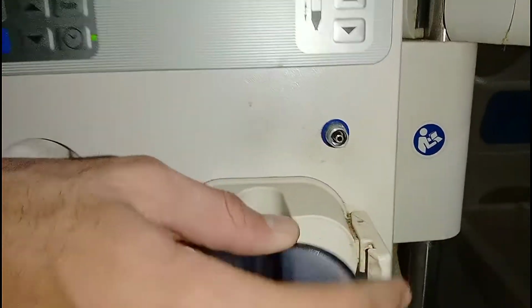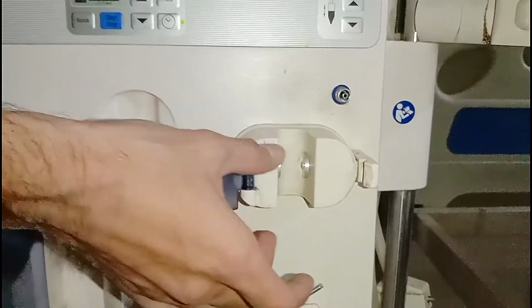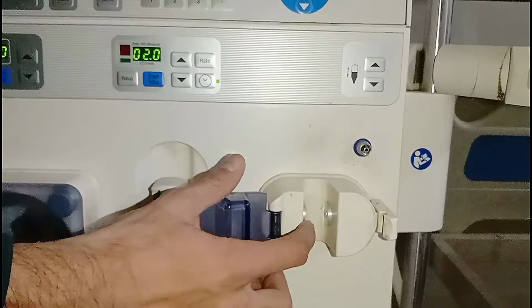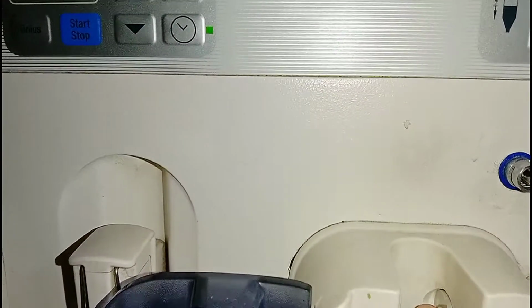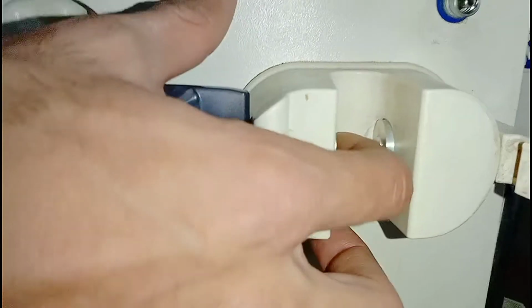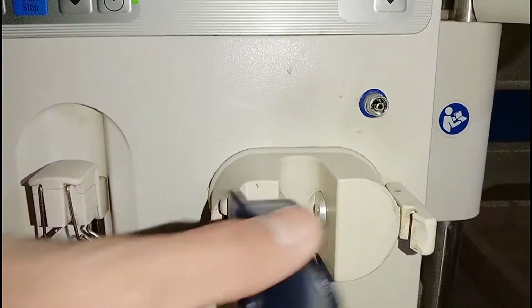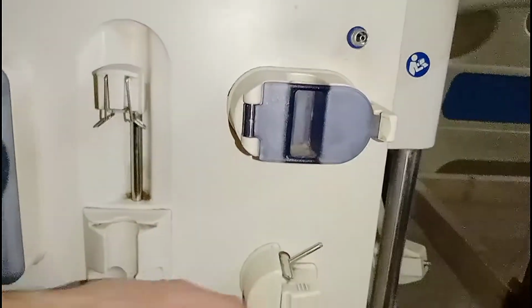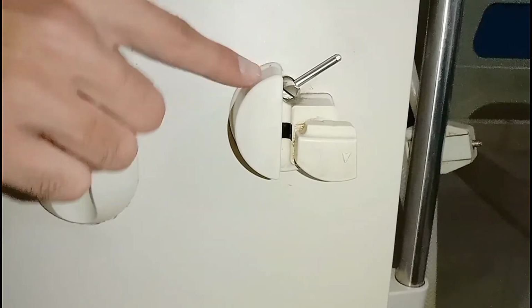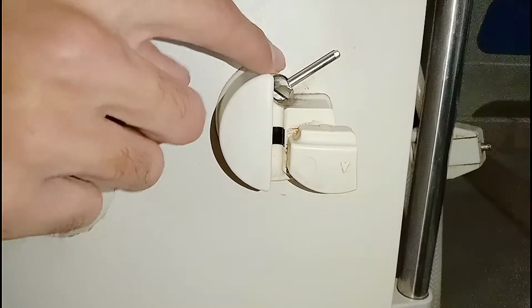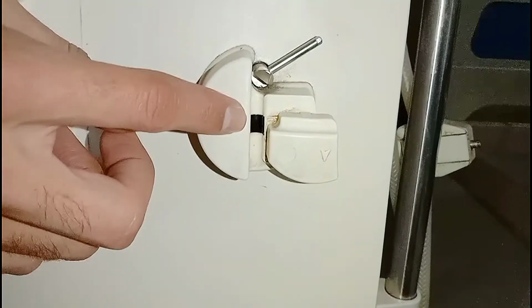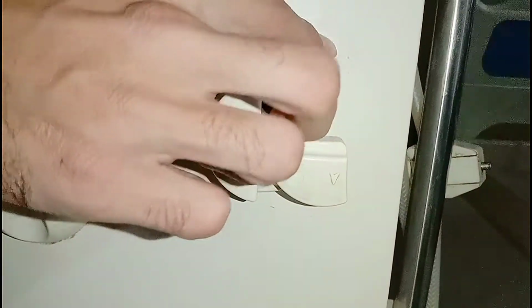And here is the venous chamber holder, the venous occlusion chamber holder. If you look inside, there is an ultrasonic sensor. It can check the level of the blood here, and it can also detect any presence of air in the venous chamber. Below this there is an optical sensor. Here it is, the optical sensor. If there is some air in the extracorporeal circuit, it will turn off the blood pump and the blood will not flow through the circuit. There is an optical detector. This will detect the presence of blood and it will occlude the clamp.